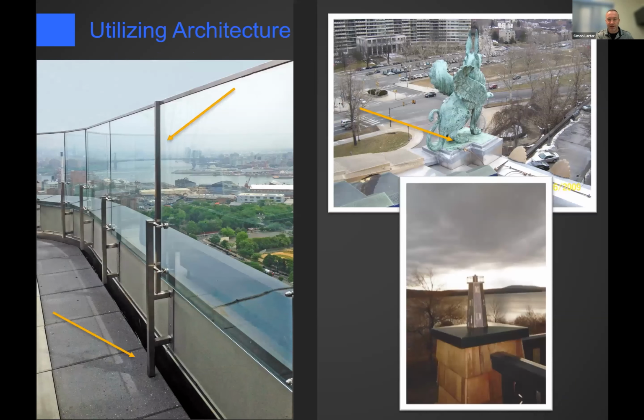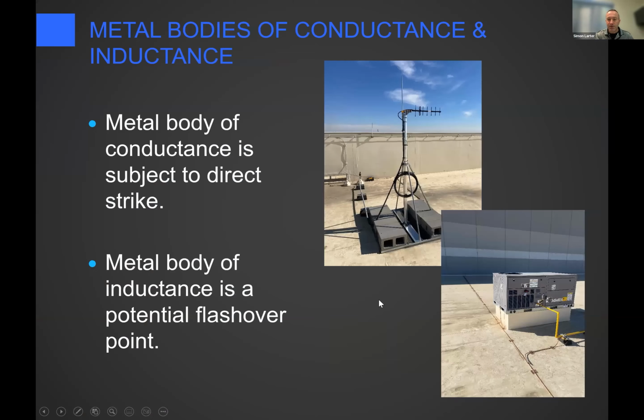Oops, get back there. That's the lower photograph. Those two pieces, they're well within the zone of protection. You can see a higher roof behind them. They are within the zone of protection. There just happens to be a conductor going across that roof to connect out to the lightning protection on the other end of the parapet that would be behind the photographer.